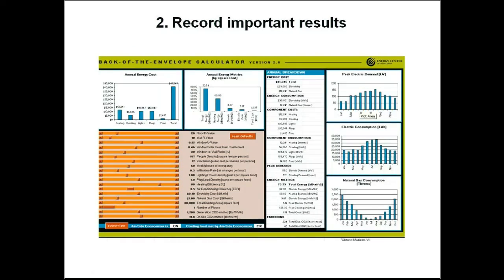Now that we have the baseline building parameters input, we want to record our important results. You may ask, what are the important results? Often it's cost, but that question is really up to you. The important results I've recorded here include the annual energy cost, annual electric consumption, natural gas consumption, peak electric and cooling demand, as well as the total CO2 emissions. It's often helpful at this point to do a quick sanity check to make sure that these values make sense. The annual energy cost comes out to about $1.40 per square foot, and that's well within the acceptable range of annual energy costs for an office. You can also double-check the consumption rates against CBECS published data from the Department of Energy.